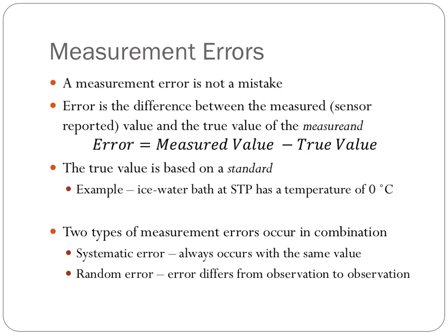You may be wondering how we get this true value. The true value of what we're trying to measure, which is called the measurand, is based on what's called a standard. A standard is something that we know to a high degree of precision has a particular value. For example, ice water that's mixed together well at standard temperature and pressure has a known temperature of zero degrees Celsius. So if I want to determine the error associated with a measurement with a transducer or a sensor that measures temperature, I can place that device into an ice water bath and know that it should have a true value of zero degrees Celsius. If my transducer does not read zero degrees Celsius, then I have some type of measurement error.